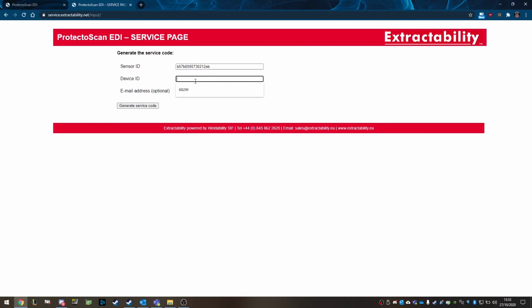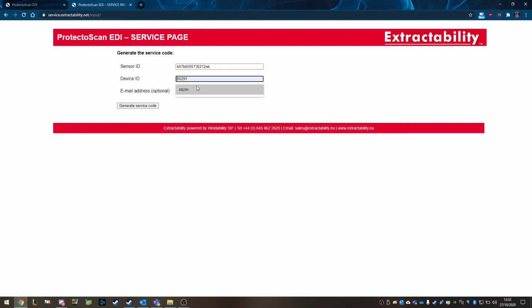Then it will ask you for the device ID. This device ID is the numbers after the ProtectoScan-EDI. So this particular unit's device ID is 00291. So we're going to put that in here. Don't put in your email address, otherwise it won't work at present. So we're just going to put in the sensor ID and the device ID.